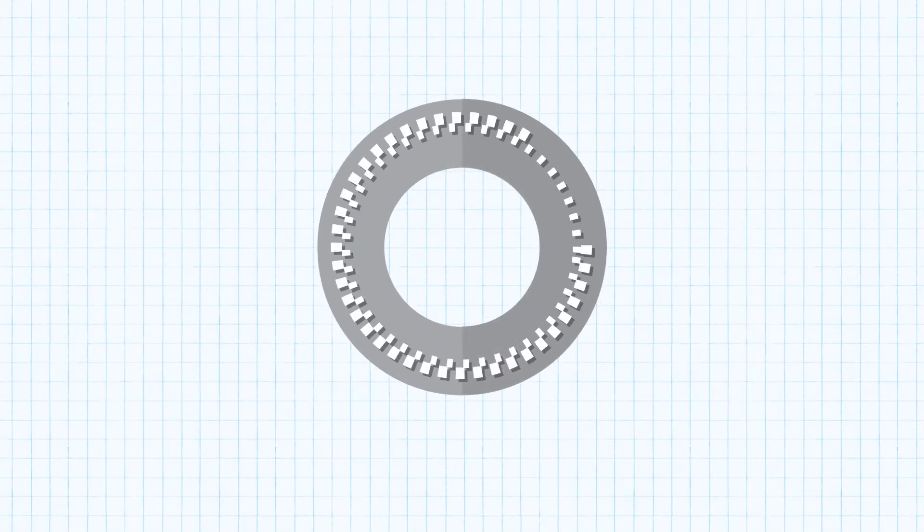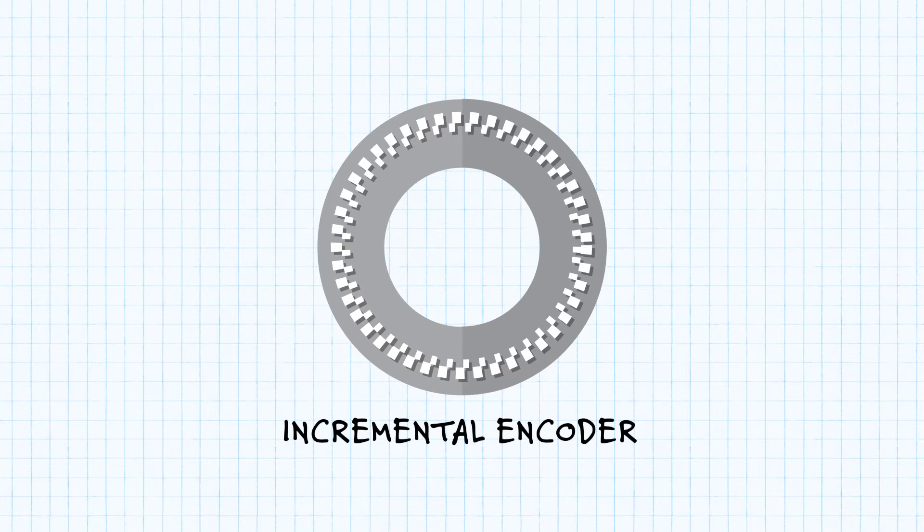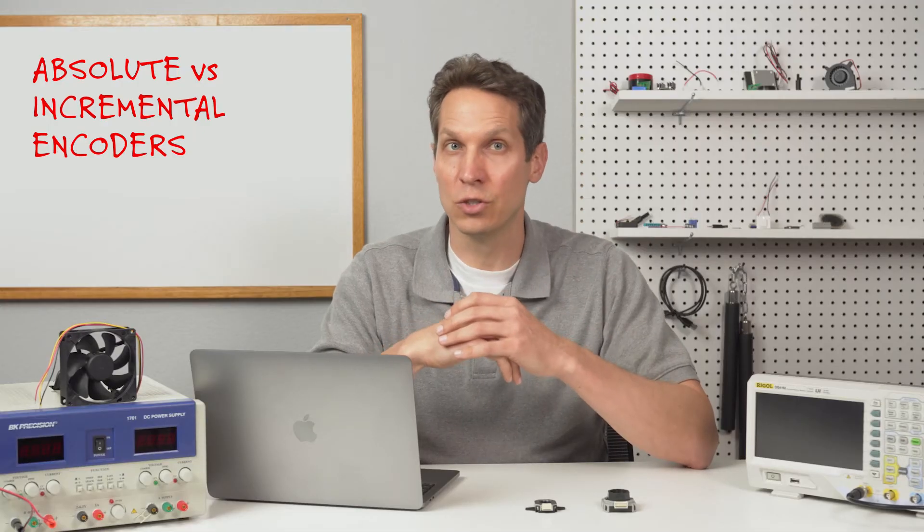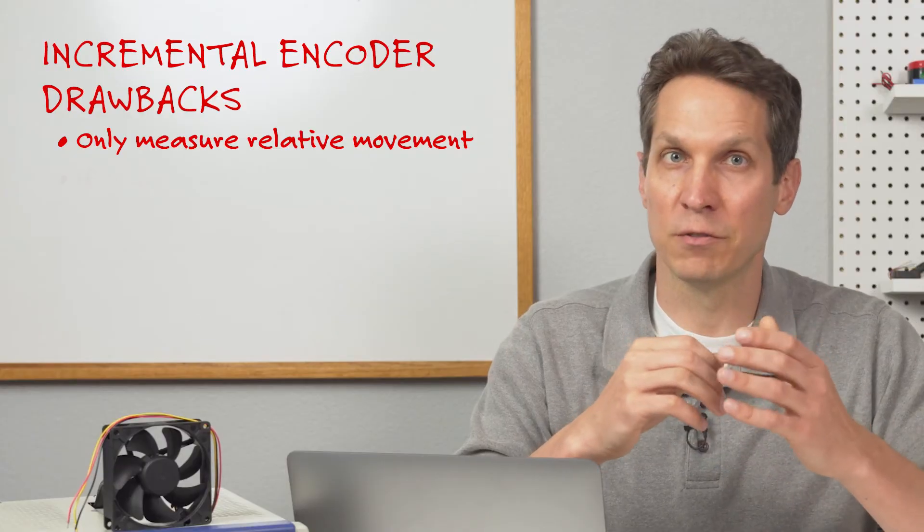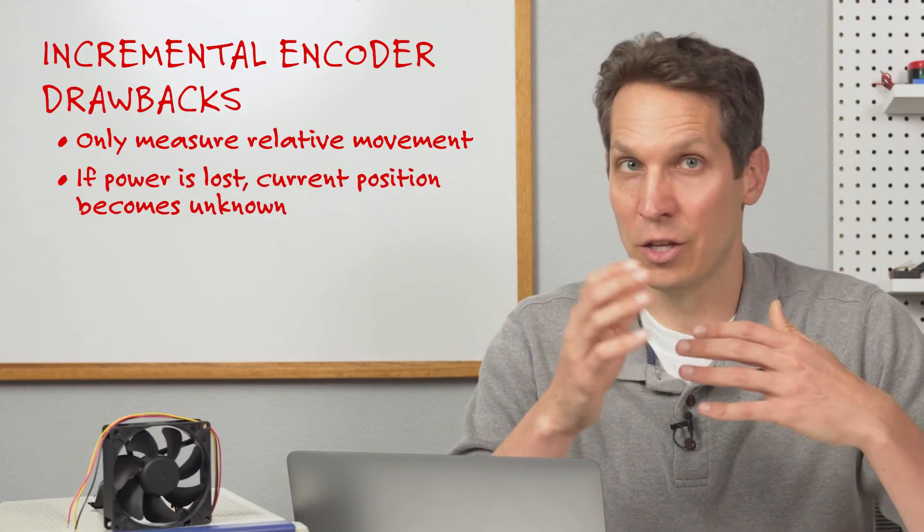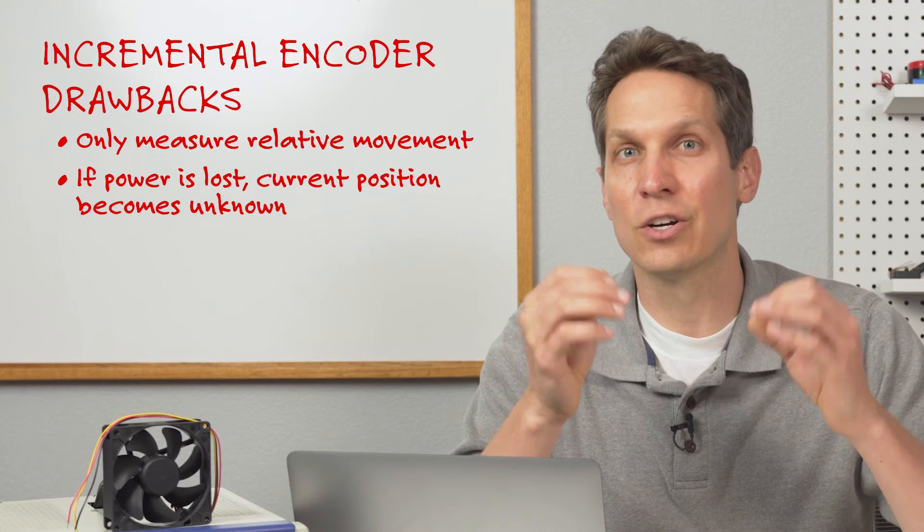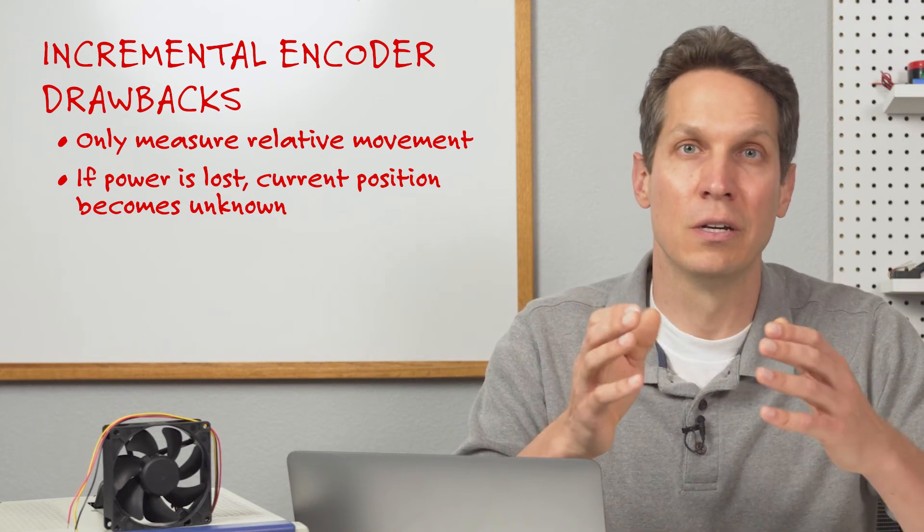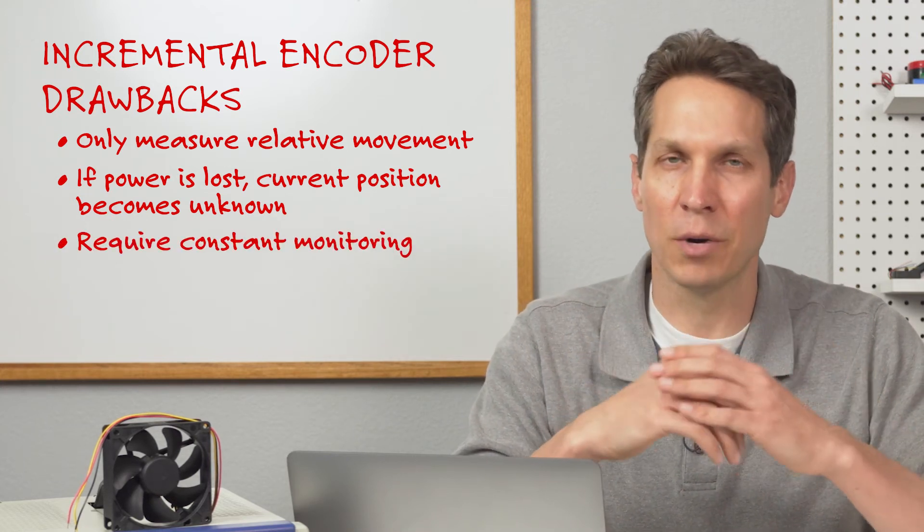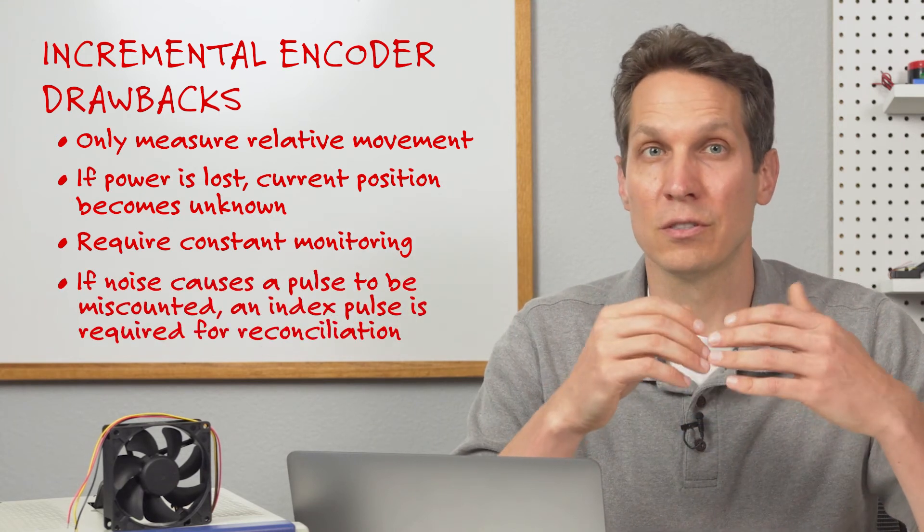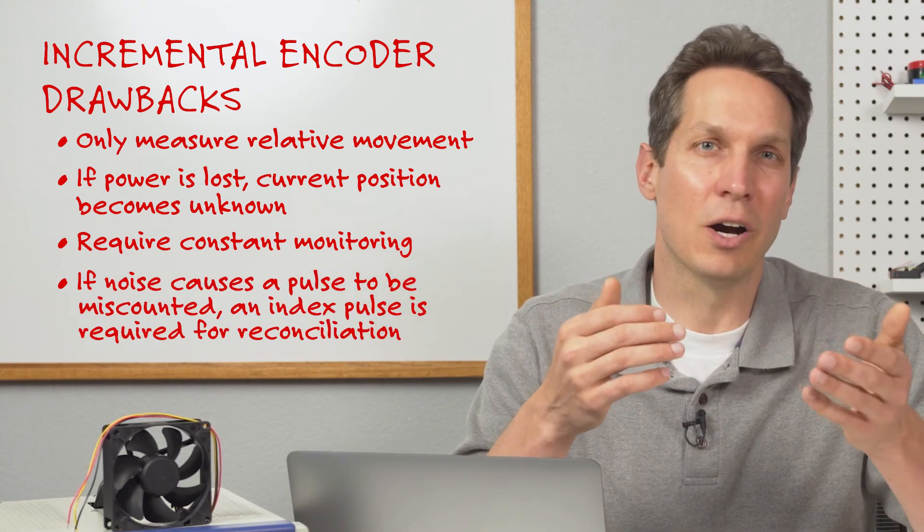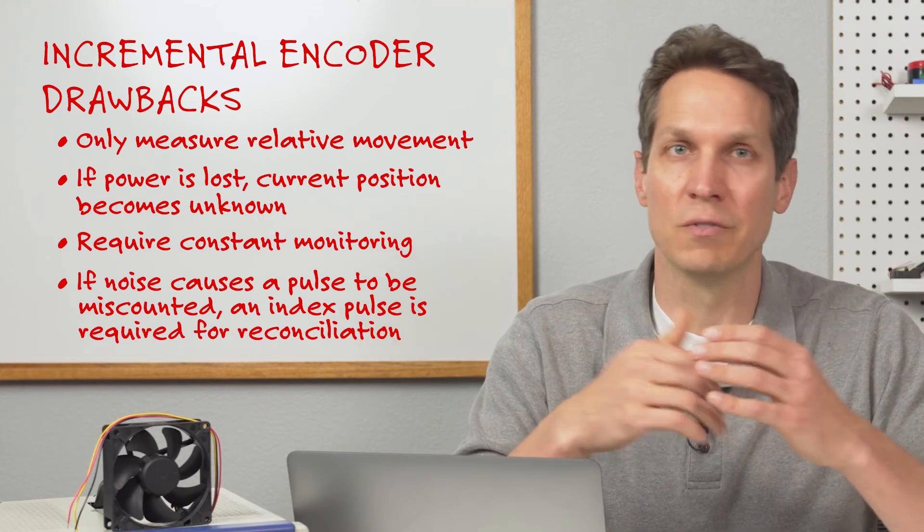Now, while the information provided by an incremental encoder is incredibly useful, there are some drawbacks due to the fact that they only measure relative movement. They only provide information if there's movement and, if there is a loss of power for whatever reason, the current position becomes unknown. They also require constant monitoring, and if there is noise that either causes a pulse to be missed or a false pulse to be counted, the position would be off and need to be reconciled with some sort of index pulse.